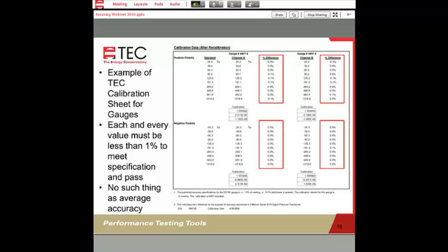Now you'll see a number of other things in here, such as the calibration. Those are our internal numbers to tell us how well the instrument over the entire range is meeting its calibration. So these are just values that we use internally to help ensure that the values that we're seeing on channel A have a proper fit and are working to your benefit, make sure that the instrument is correct.